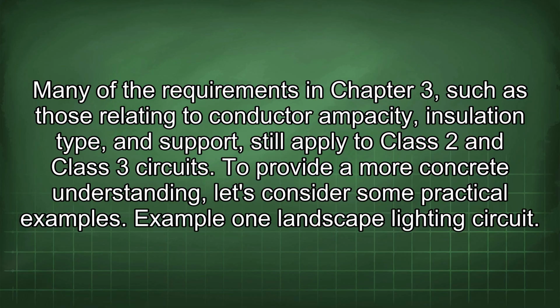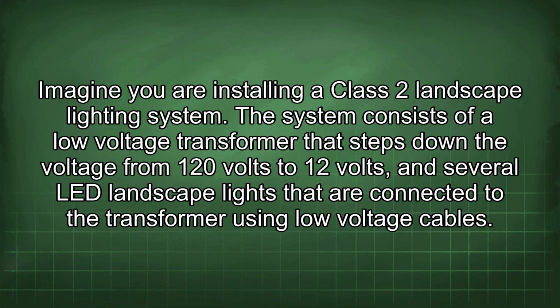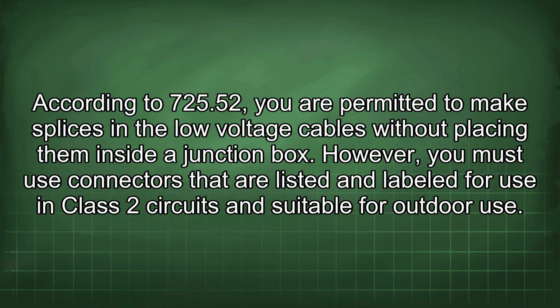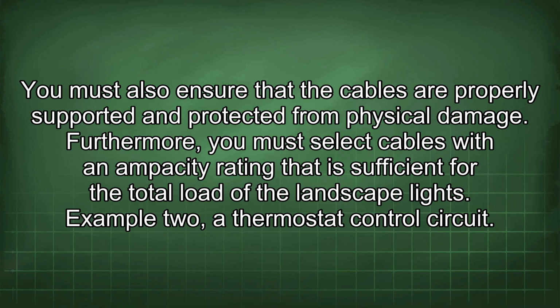To provide a more concrete understanding, let's consider some practical examples. Example 1: Landscape lighting circuit. Imagine you are installing a Class 2 landscape lighting system. The system consists of a low-voltage transformer that steps down the voltage from 120 volts to 12 volts, and several LED landscape lights that are connected to the transformer using low-voltage cables. According to 725.52, you are permitted to make splices in the low-voltage cables without placing them inside a junction box. However, you must use connectors that are listed and labeled for use in Class 2 circuits and suitable for outdoor use. You must also ensure that the cables are properly supported and protected from physical damage. Furthermore, you must select cables with an ampacity rating that is sufficient for the total load of the landscape lights.